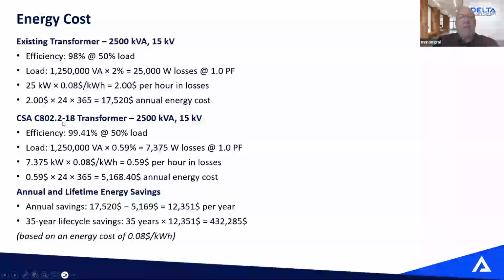If you go to, I would say, the latest efficiency transformer, same criteria. In that CSA table, we see that the efficiency at 50% load is 99.41. So same maths: at 50% load times my efficiency, that's my losses at 1 PF. Those losses times 8 cents a kilowatt, I'm at barely 60 cents an hour, per day, per year. For a year, I'm at about $5,168 in cost of energy. So you save about 12 grand per year on losses burnt in that single transformer.